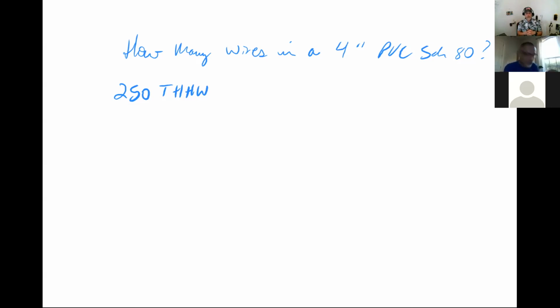Okay, so you were correct. You did start to talk about the Schedule 80, right? In this case, that's our fixed value, because that's what's going to limit how many wires we're fitting in there. So we do want to look for the allowable fill area of a Schedule 80 PVC conduit. In conduit fill, it's either 60% if it's a short length, 40% if it's more than 2 wires, which this probably will be, or in some rare cases, it could be 31% or 53%.